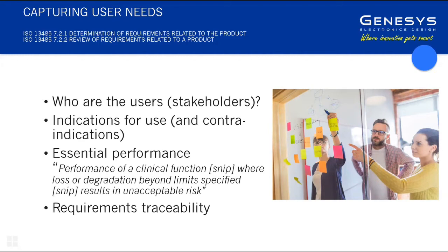But it also encompasses the manufacturer of the device, the medical device manufacturer, and perhaps you can even consider their investors may have needs that need to be satisfied. The requirements of all of these parties can be captured as user needs. The importance of doing so, which we'll talk about in more detail in the presentation, is that the user needs are the starting point of a traceability process of requirements throughout the hierarchy of design documents. It's incredibly important to get them correct.